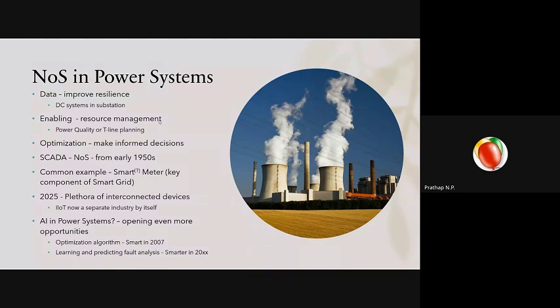You would monitor the current flow in a transmission line, and also take in weather data. Weather data comes from a sensor, and load flow comes from CTs and PTs. Then you make a comparison saying, okay, maybe only during summers this transmission line is getting overloaded. So maybe we should allocate more generation resources during summer, or if there are no other resources, put in a parallel transmission line. So it helps in long-term planning.